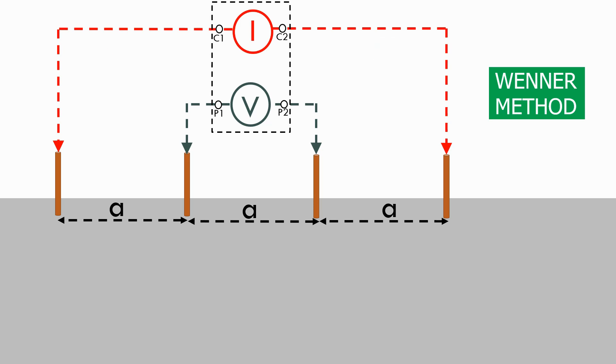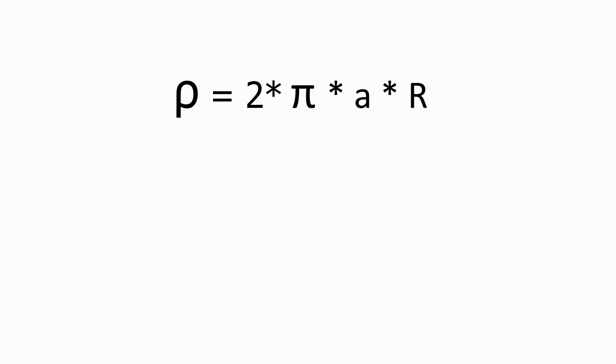We can then convert this resistance value R into a soil resistivity measurement using the following formula. The soil resistivity, ρ, equals 2 times π times A times R.